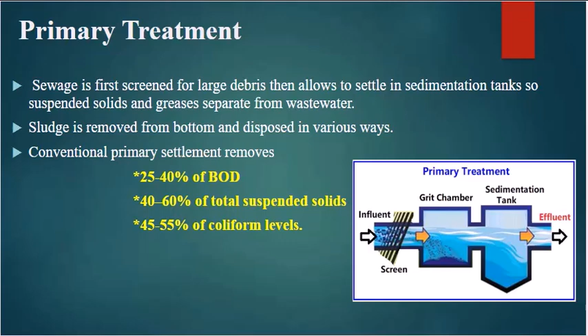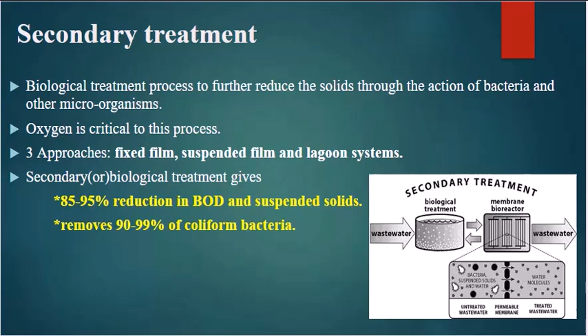Secondary treatment. Secondary treatment utilizes biological processes to reduce organic material in wastewater. Oxygen is critical during this phase to support bacterial activity. Common methods include fixed film systems, suspended film systems, and lagoon systems. This treatment can result in an impressive 85 to 95% reduction in biochemical oxygen demand and suspended solids, with 90 to 99% of coliform bacteria removed, making it a vital step in the treatment process.